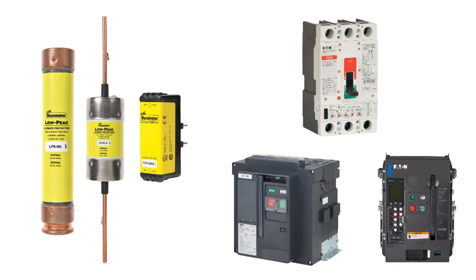Shown here are the UL 248 listed fuses along with UL 489 molded case circuit breakers and UL 1066 insulated case and power circuit breakers that provide acceptable branch circuit protection. The UL 248 fuse standards cover distinct low voltage fuse classes below 600 volts AC. Of these, modern current limiting fuse classes CC, CF, G, J, L, R, and T are the most important.